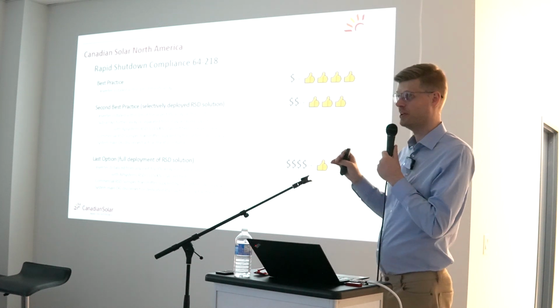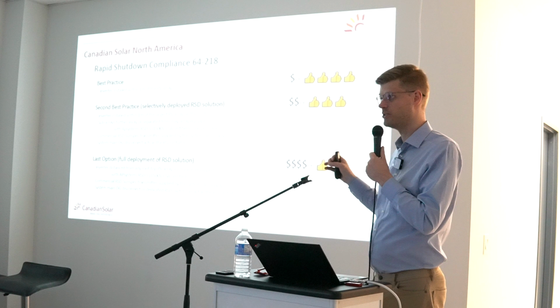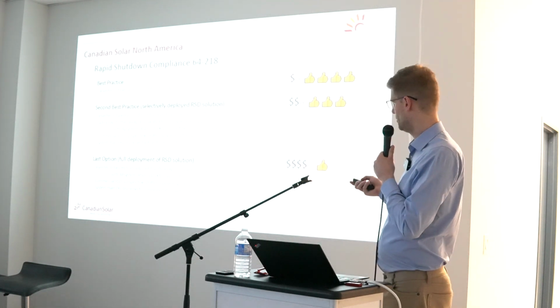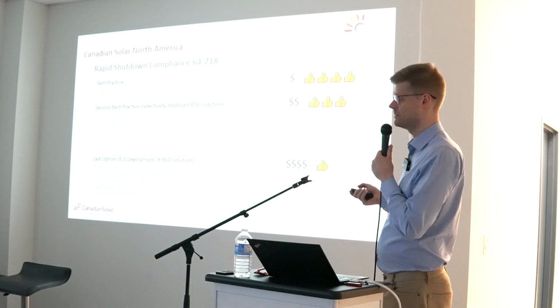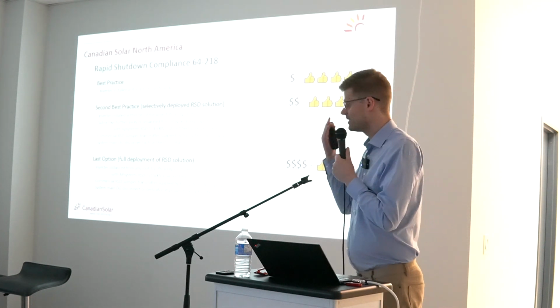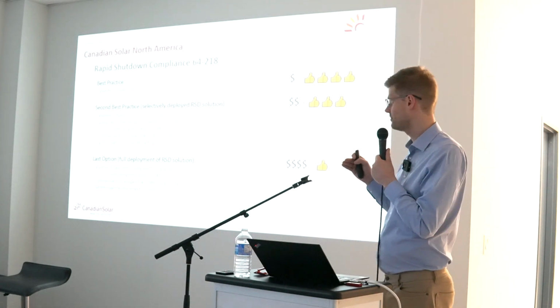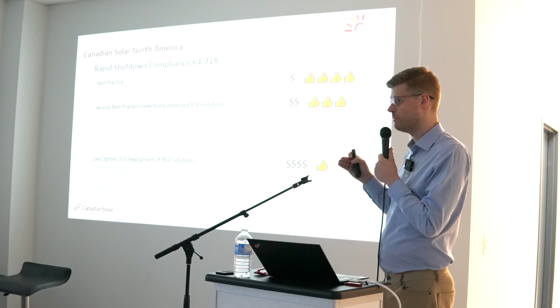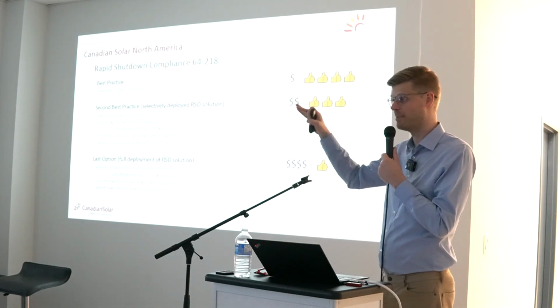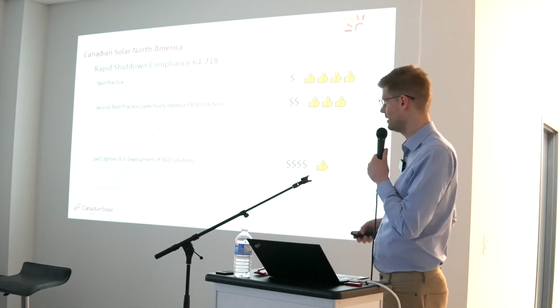And the smaller sub-arrays, these ones you can treat with panel level rapid shutdown, certified to 1,500 volts. That would typically be an AP Systems RSDS device. And this way you still have the least number of components in your system. You have a very reliable system, but you're still code compliant for both the large as well as the sub-arrays on part of the other roofs.